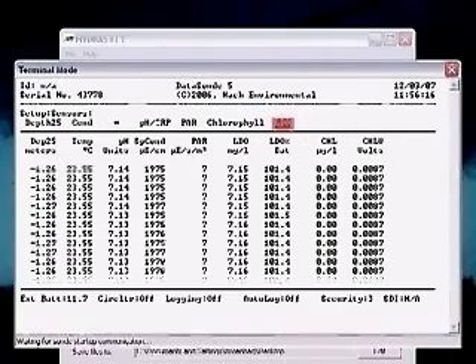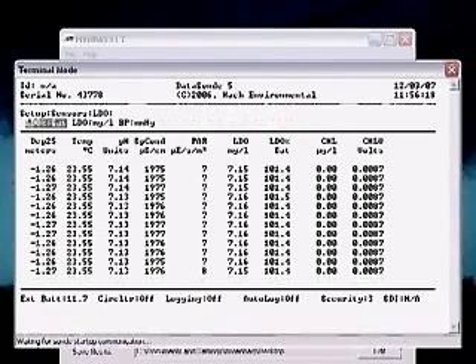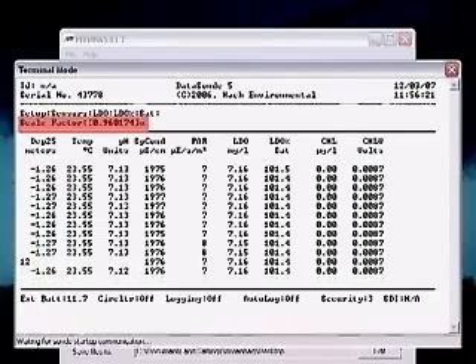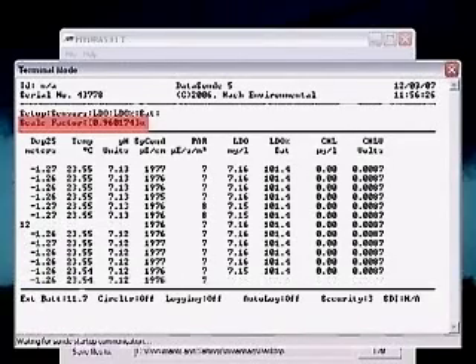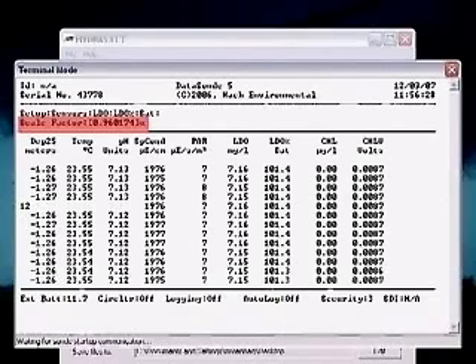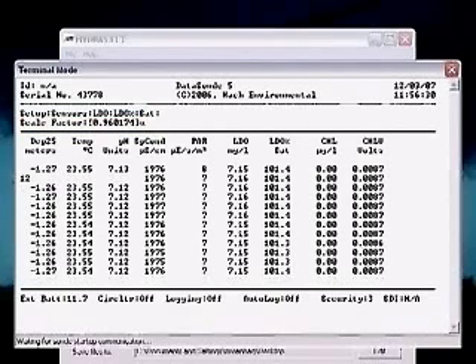Highlight LDO and press Enter. Highlight LDO %SAT and press Enter. Read the scale factor. A valid calibration will produce a scale factor between 0.5 and 1.5. Values outside of these parameters may indicate a problem with the sensor or electronics.